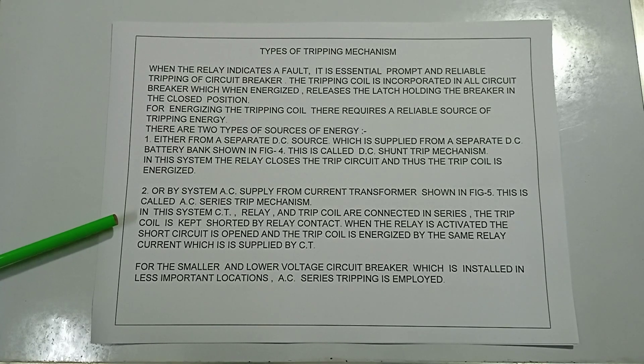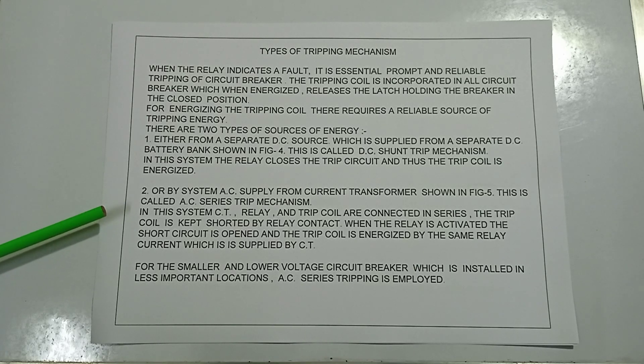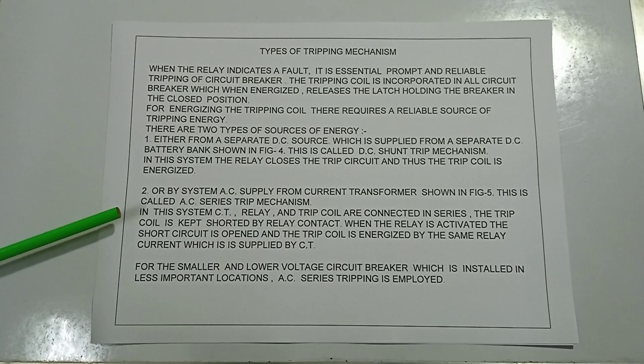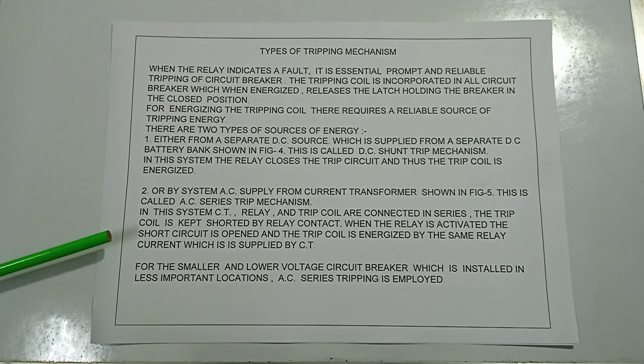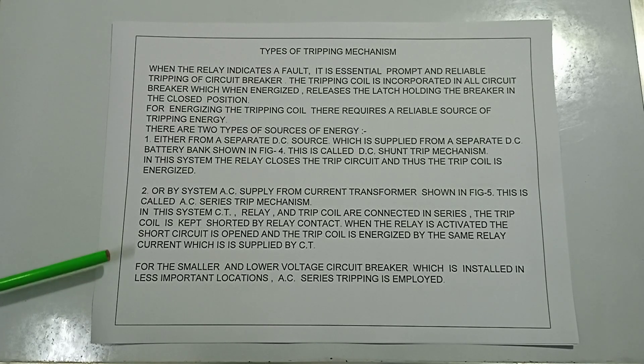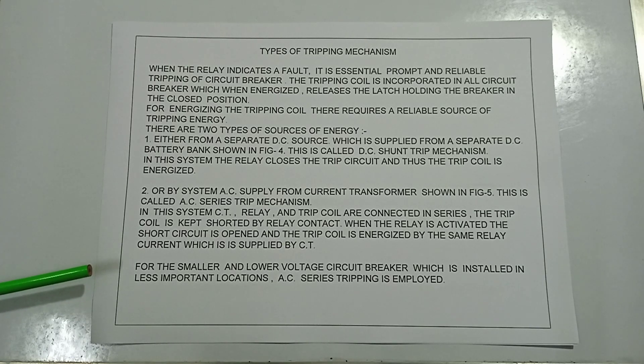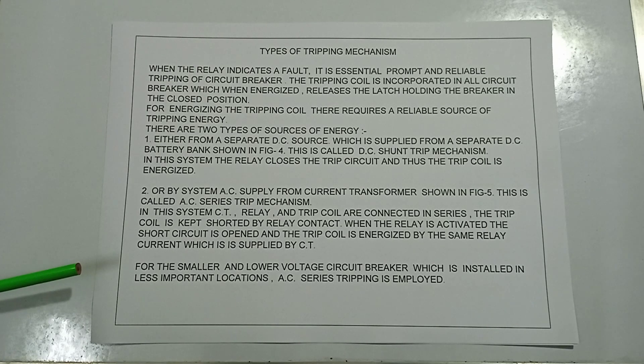In the AC series trip mechanism, the trip coil is kept shorted by the relay contact under normal conditions. When the relay is activated, the short circuit is opened and the trip coil is energized by the same relay current supplied by the CT. For smaller and lower-voltage circuit breakers installed in less important locations, AC series tripping is employed.